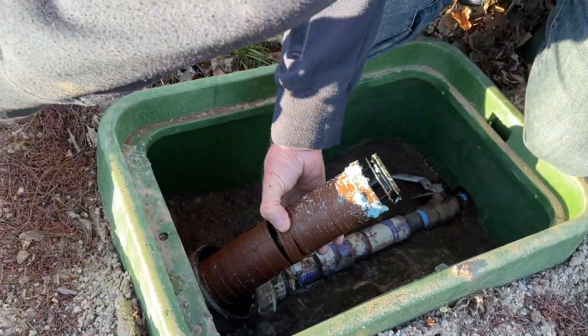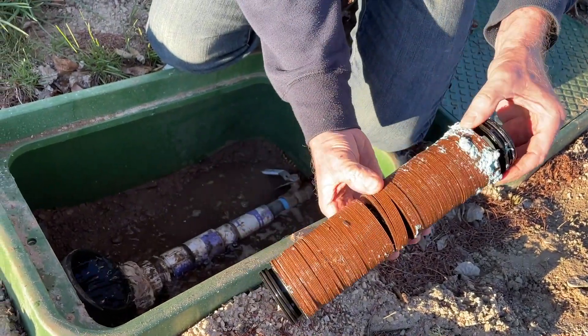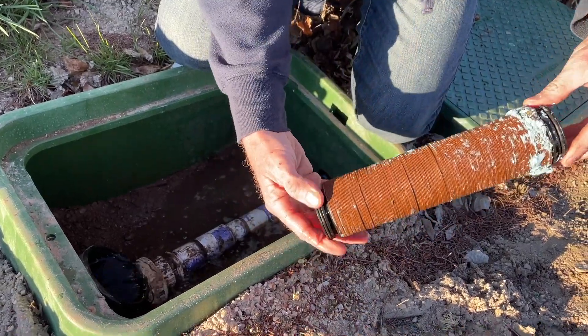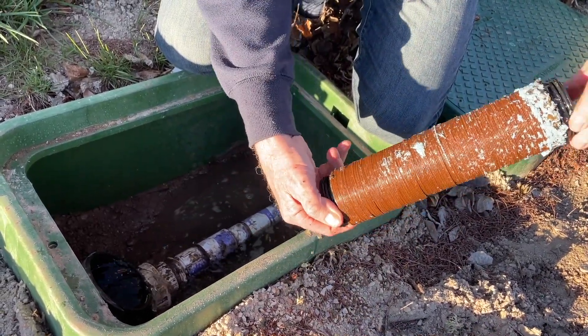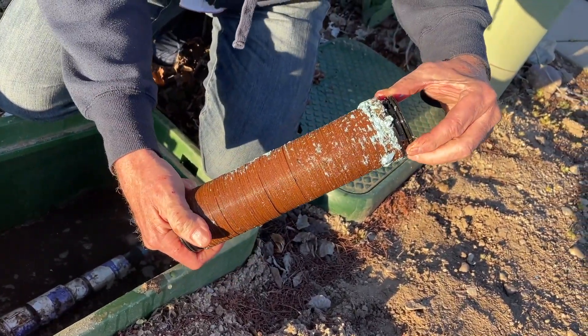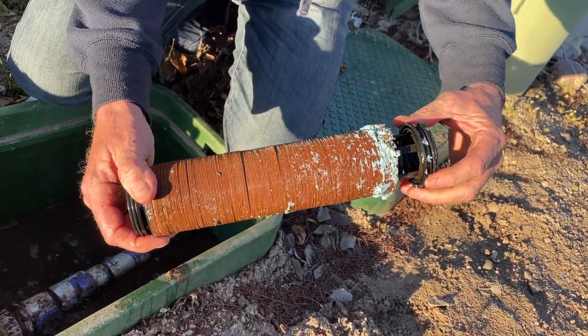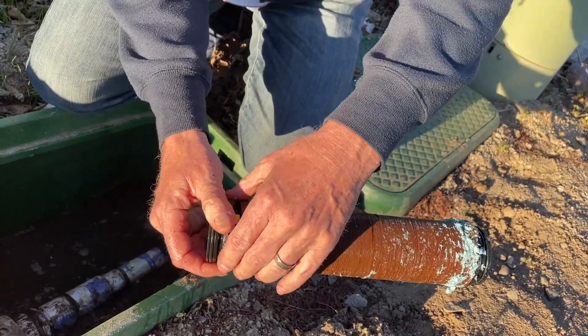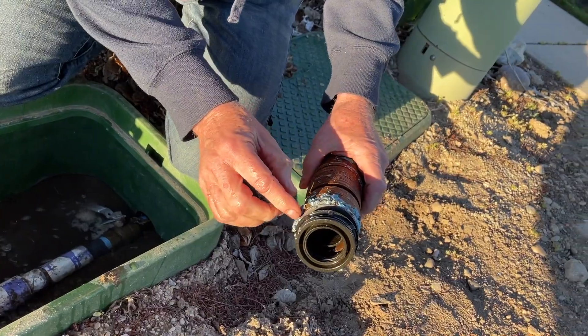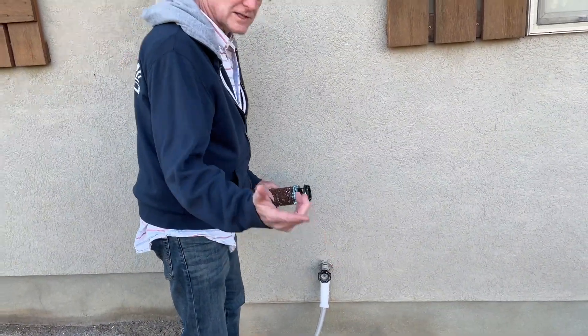The filter looks like it's got all kinds of junk — I don't normally see this in here. I think this stuff is probably glue from the system. Normally this thing is held tight, but that holds these little discs together. We're going to take it over to the hose — it doesn't come off completely, but it allows these discs to rotate freely — and we're going to spray this all off and get the gunk off.